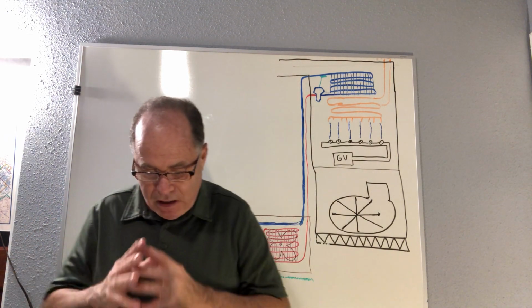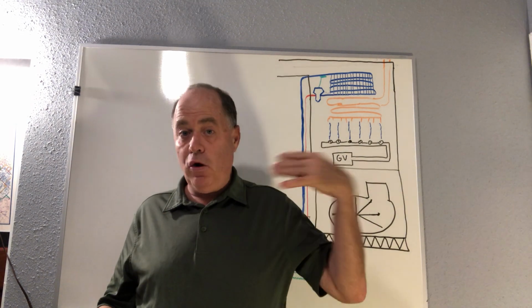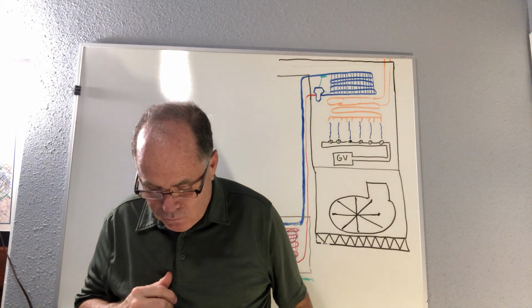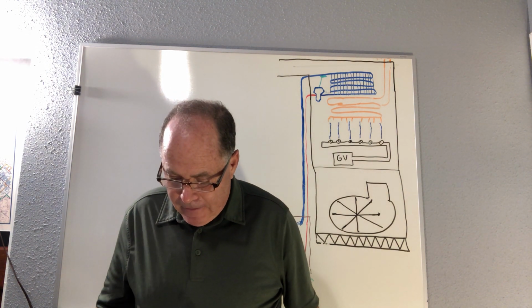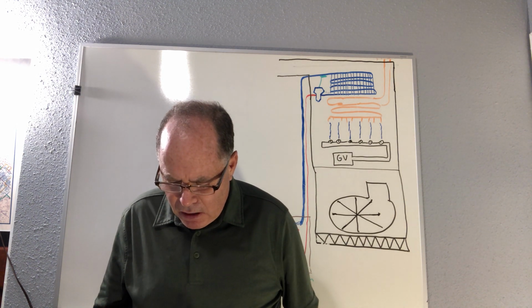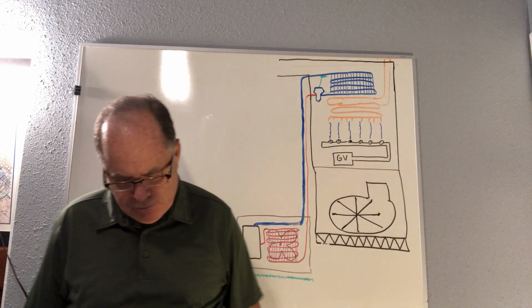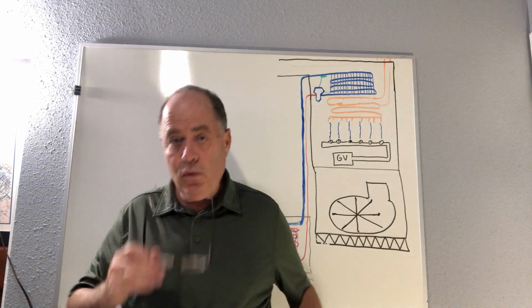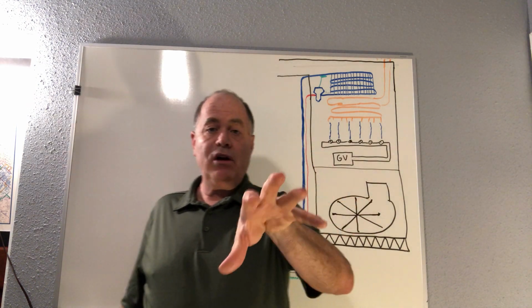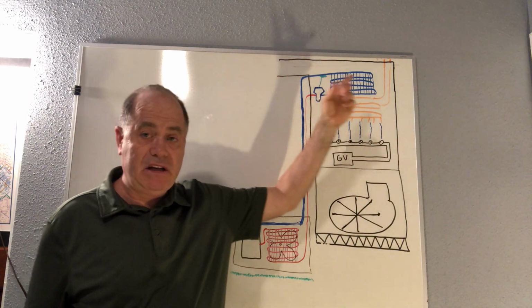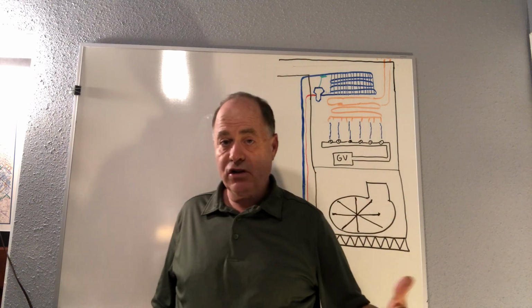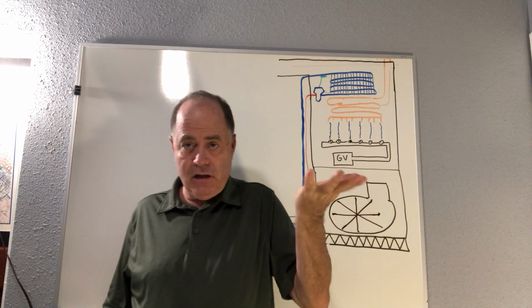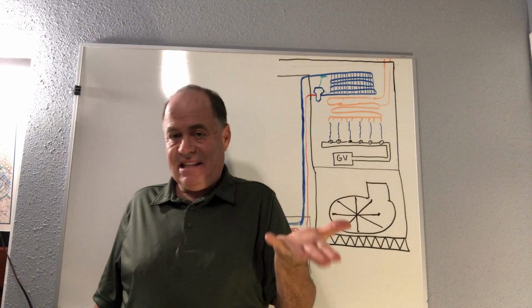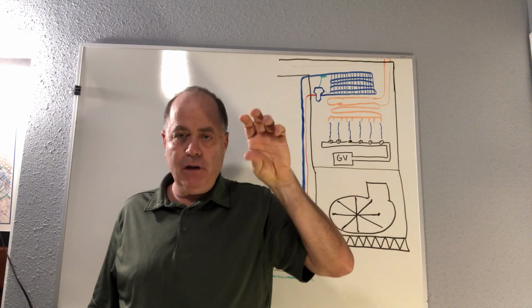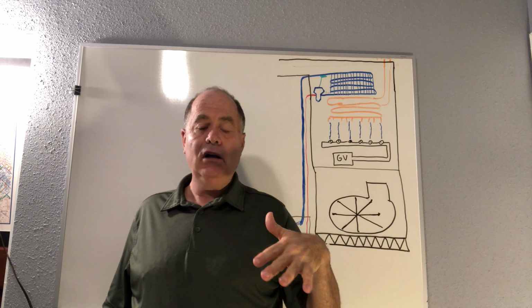Okay, temperature pressure limiting devices. We have temperature pressure limiting devices where if you get over temperature, over pressure, we're going to relieve the pressure. So really we're talking here more about limit switches, where it's going to shut down with excess pressure for a boiler or temperature for a furnace, which would be like 250 degrees right here. We're going to have that. And then we're also, for boilers, going to have a low water cutoff, where usually a boiler is partially filled with water. And then if you're making steam, then the top portion of the boiler is steam, and we have a float switch that is going to shut the boiler off if you get low on water for safety.